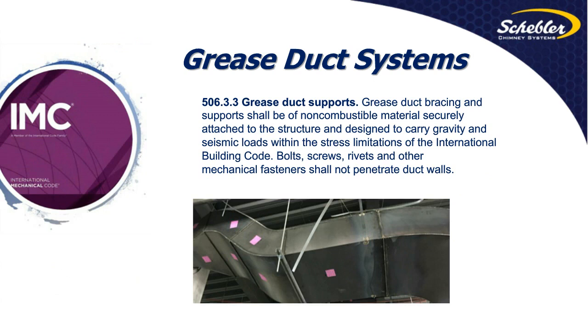Supports mentioned in the International Mechanical Code, it's very vague on exactly how this thing should be supported. Really basically pulling from the code, as long as the structure is able to carry the load and seismic loads and stresses in the building code, we're going to say the supports are acceptable. And then they will note that bolts, screws, rivets, and other things can't penetrate the ductwork, but it's really vague on what those supports should look like to properly keep the ductwork in place, especially in the event that we would have a fire, either in the kitchen or in the ductwork.